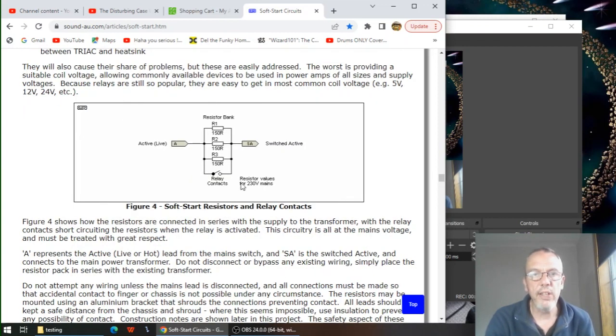Further up the page, this is what the resistor bank is made up of: three 150 ohm resistors in parallel, which gives us a total of 50 ohm in the end, and 15 watts. So as we can see, the active comes in through the resistor bank out to the switched active, which goes to the transformer, and as soon as the relay contacts close, it shorts that resistor bank out, allowing the current to flow through directly to our load.